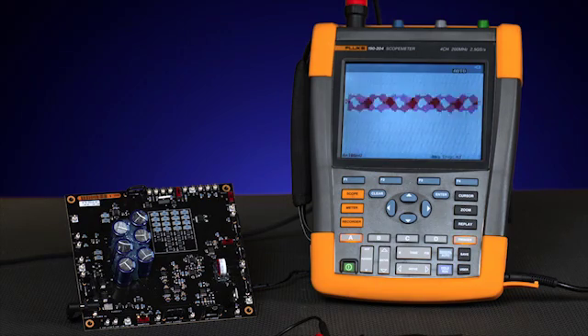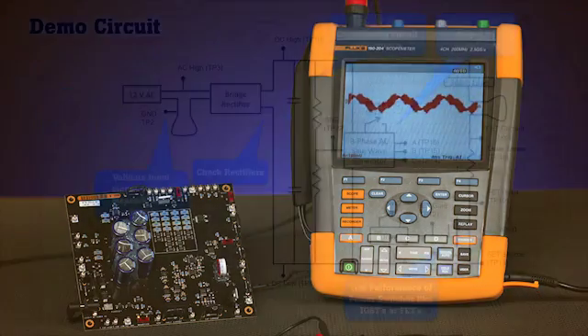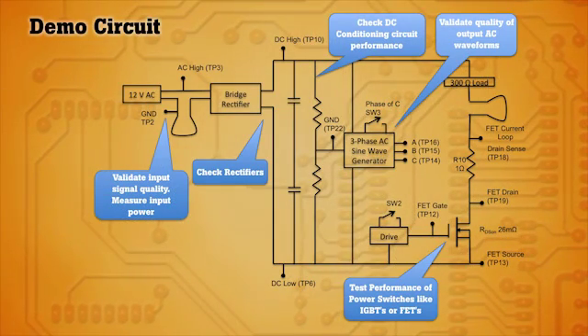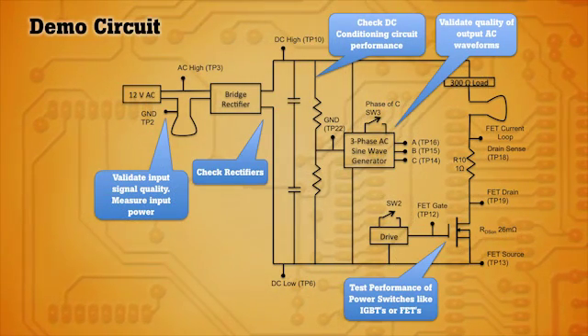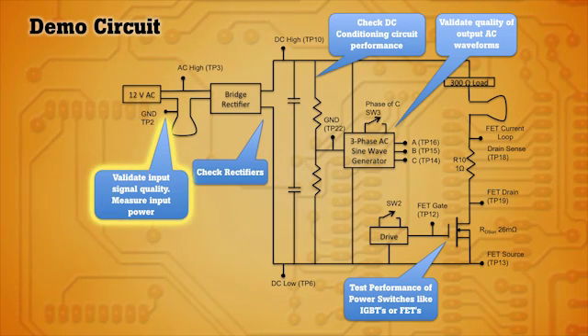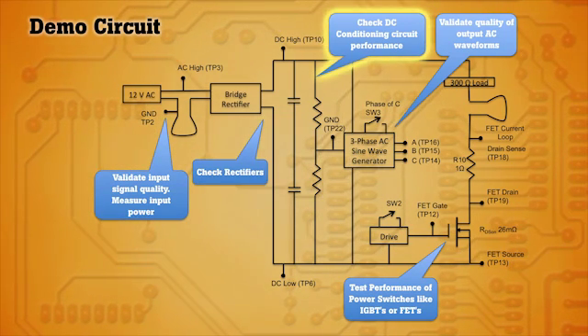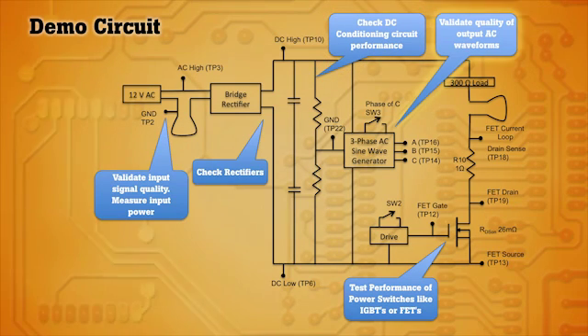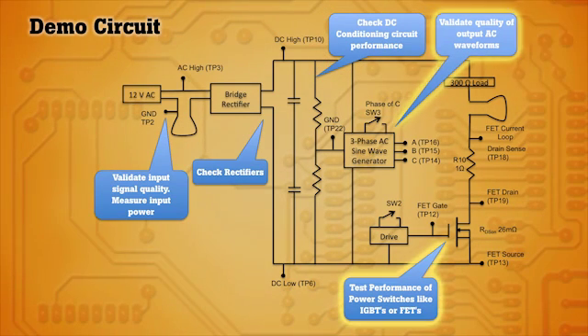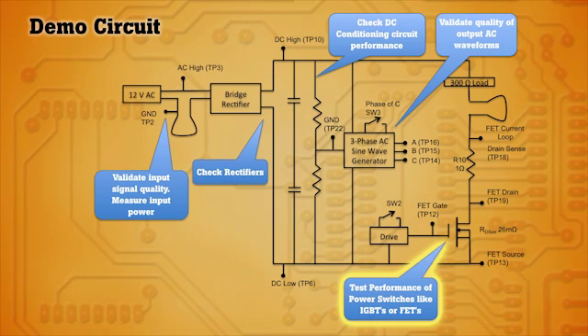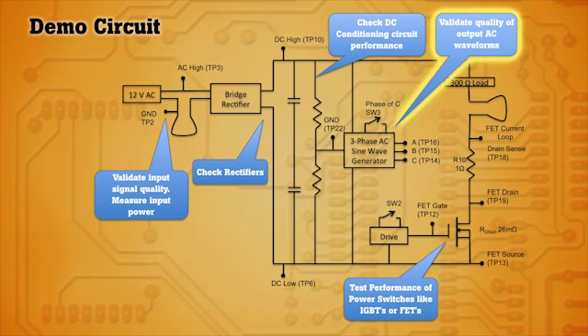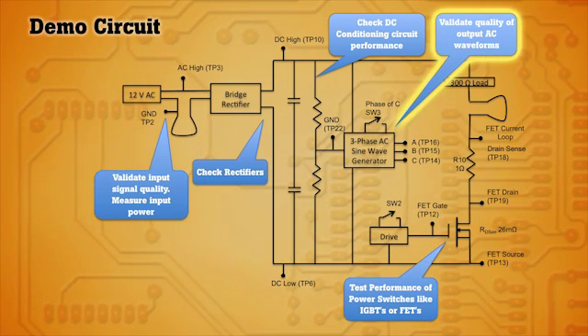The demo board we're using today is a basic inverter circuit that you might find in industrial power electronic systems. It starts with the input circuit. The AC goes through a bridge rectifier creating a DC bus that will then be used in the inverter circuit. Switches or high-powered switches modulate this DC bus to provide an AC waveform on the output of the board.